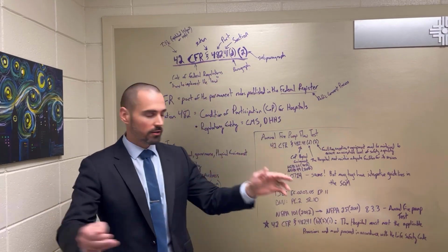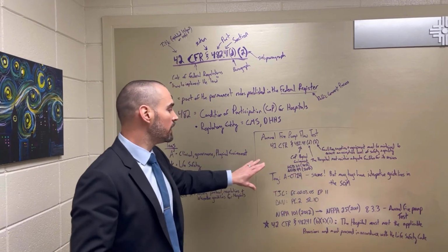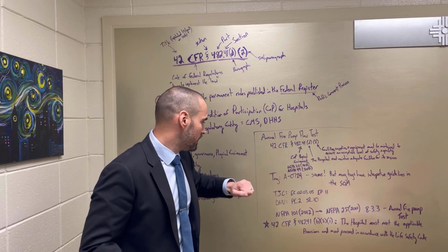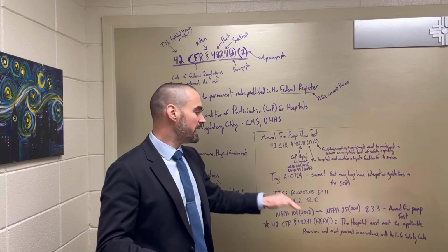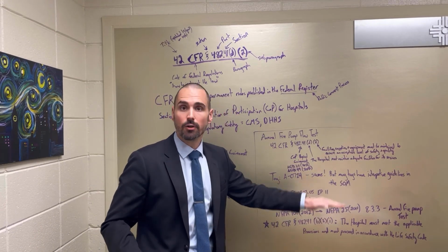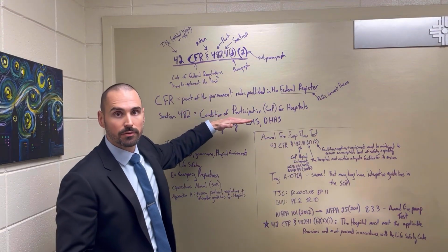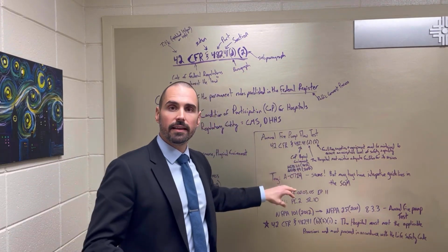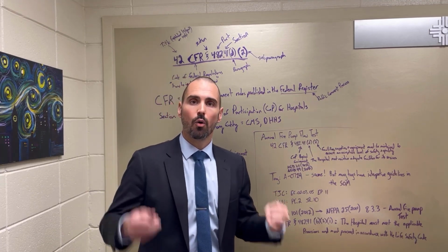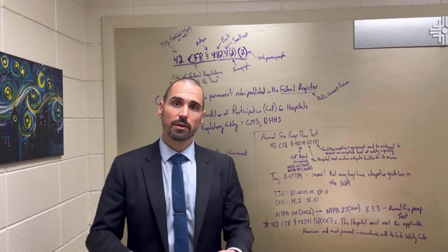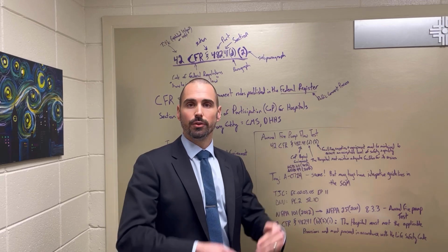So, to clear this all up, this is the key. This is where I said we're going to come back to, right? Okay, to clear all of this up, stop following the prescriptions from your accrediting organizations. You can use that for organization and such, but if you are meeting the provisions of the code itself, then you are in compliance with the condition of participation for hospitals. So only look at your accrediting organization or your A-tags, or however you are organizing it, from an organizational perspective only. When you have questions about the actual technical requirements for an ITM program, go back to the code.